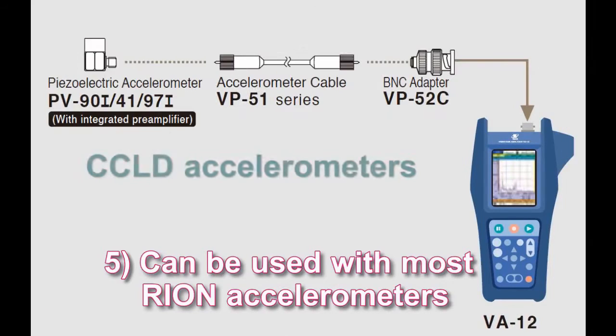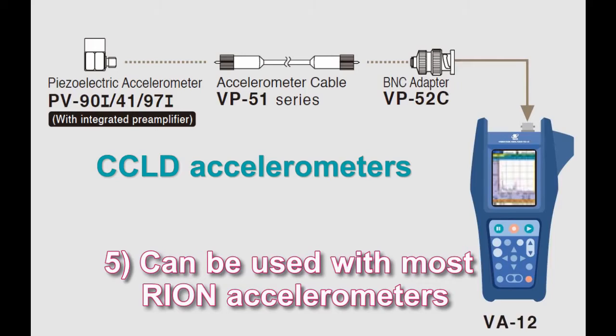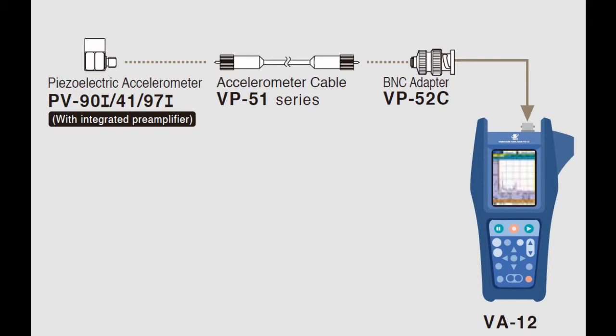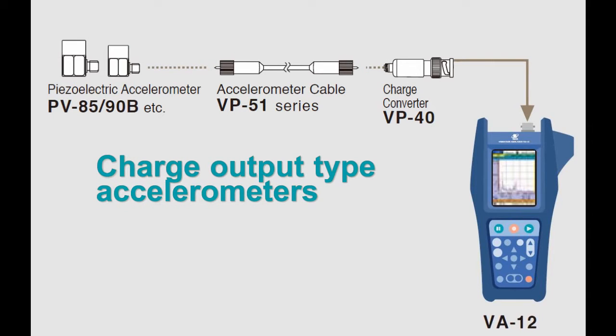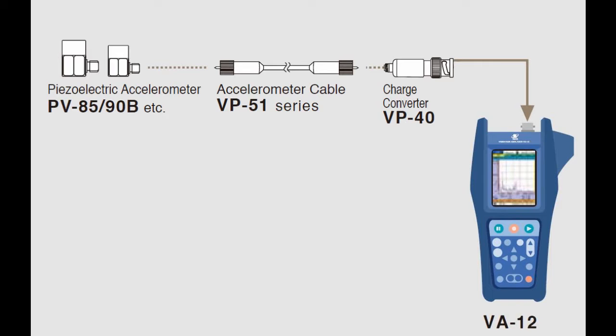Feature five: The VA-12 can be used with most Rion accelerometers. CC-LD accelerometers with integrated preamplifiers can be connected using a BNC adapter. Charge output type accelerometers can be connected using a VP40 charge converter.